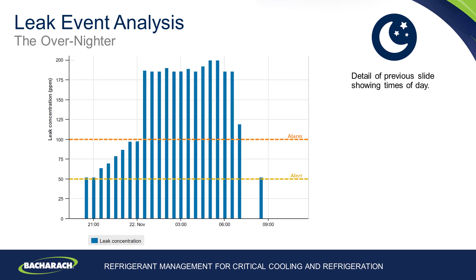Looking at that same leak pattern in more detail over a 12-hour period — from 9pm the PPM values rise as that walk-in cooler is used less and less. Over the overnight period between midnight and 6am, when it is completely closed, the PPM values rise. The values, up to 200 PPM, are not large, but even though they are not huge PPM values, a leak is there. If we can identify it and rectify it quickly and easily, we will reduce refrigerant loss immensely.